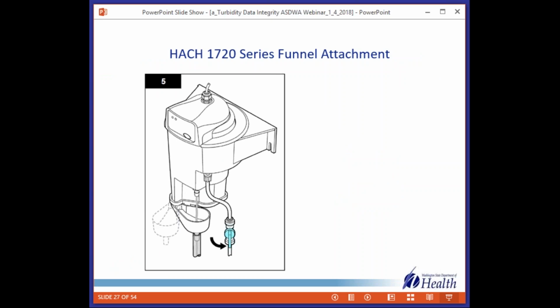So we like to see an air gap here. This is an example of a commercial attachment that you can buy, but I'm sure you could make something like this. So right in there is the air gap, so you can get your sample bottle in there to collect the sample. You can also visually see that you have flow going through the turbidimeter, and that's a location where you can sample the flow rate or measure the flow rate to make sure it's within the manufacturer's specification.